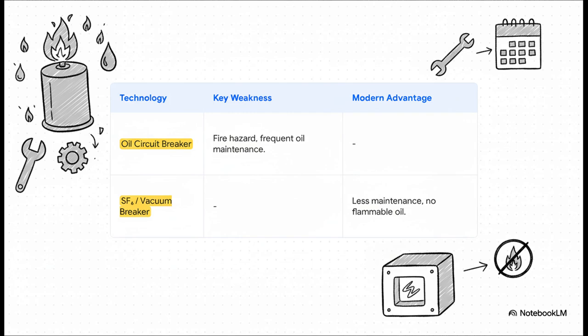Well, the answer really boils down to two things: risk and maintenance. First, you can't get around the fact that a huge tank of flammable oil is a fire hazard. It just is. And second, these things require a ton of upkeep. You have to constantly test the oil to make sure it's not contaminated and to check its dielectric strength, which is just a measure of how well it's insulating.